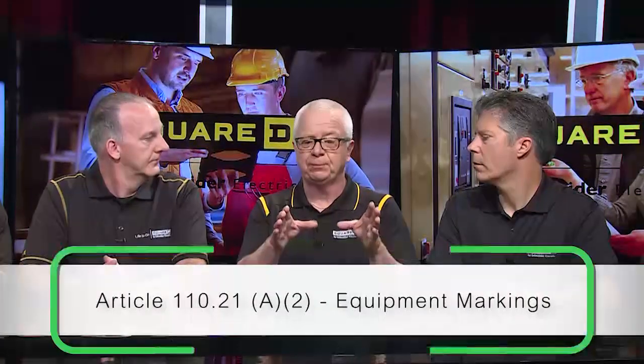If I've got equipment that, for example, goes underwater in a flood in Florida, and somebody buys it and it goes to Minnesota, now they've reconditioned it because it's not in operational condition. Now we've got a piece of reconditioned equipment that may be for sale. And there's a marking requirement that's going to significantly impact any reconditioned equipment, and we'll go to Mike for that.